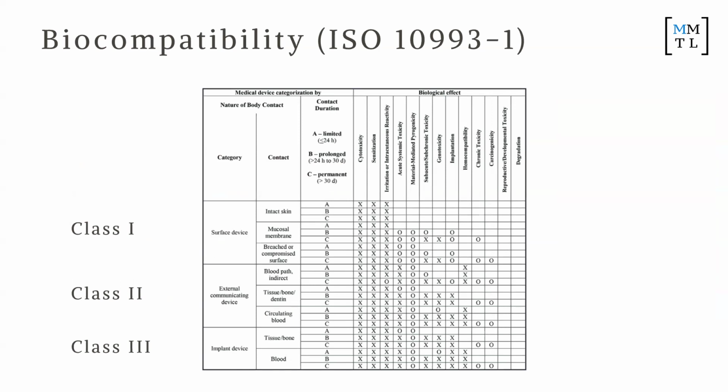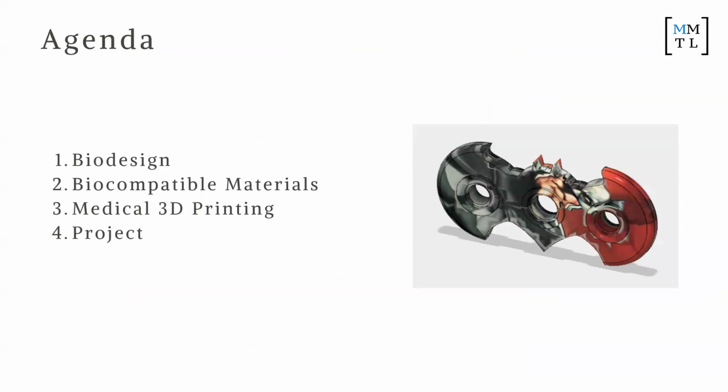All right, again, back to the biocompatibility thing, but do be aware of what exactly you're intending to use it for, and make sure that you use a biomaterial of the appropriate class. Okay, so whenever you're looking up biocompatible materials, it will always specify what class it is, okay? And that corresponds to what you intend to use it for. All right, so finally, let's go into the project.